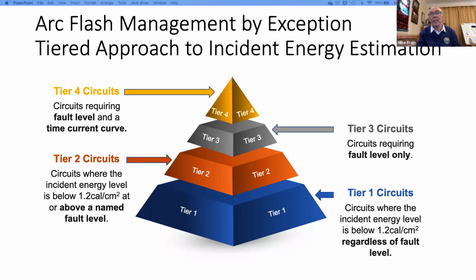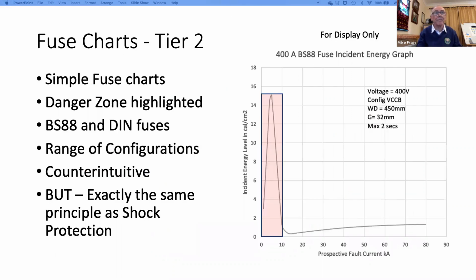Tier 3 circuits, we need just a fault level only to work that out. So we need an accurate reading for the fault level at that point. And then tier 4 circuits, we need the fault level, and we will need a time current curve at that point. And the reason I've put them into that sort of pyramid is because, as you can see from that, the tier 4 circuits are very much smaller than the rest. And I would hope, from a duty holder, that's the concentration that he'll have to use.